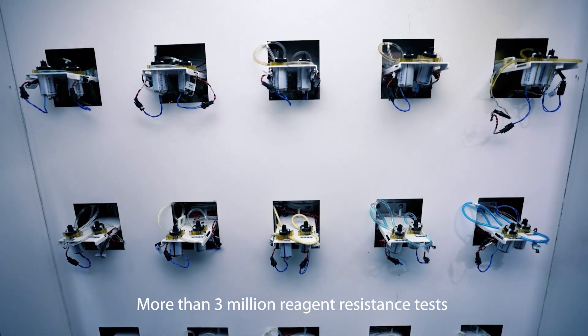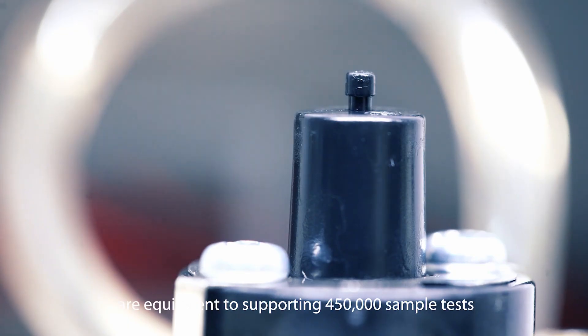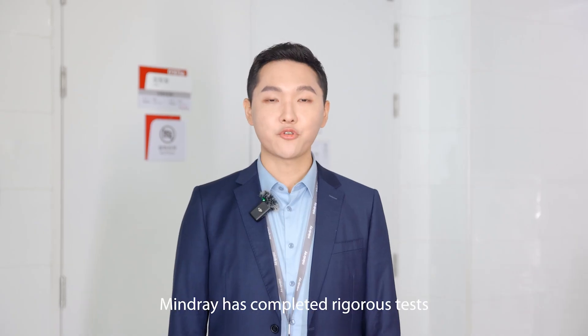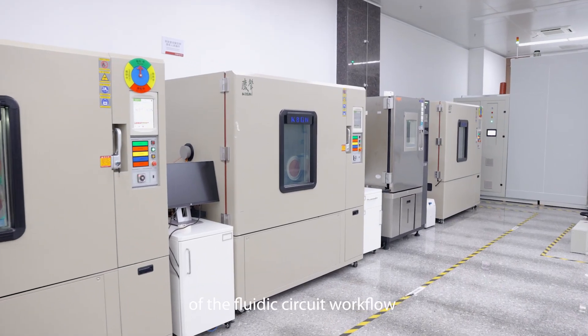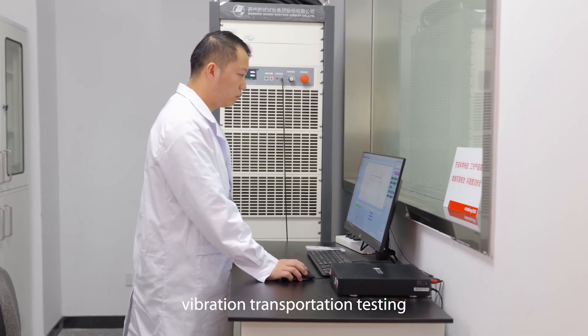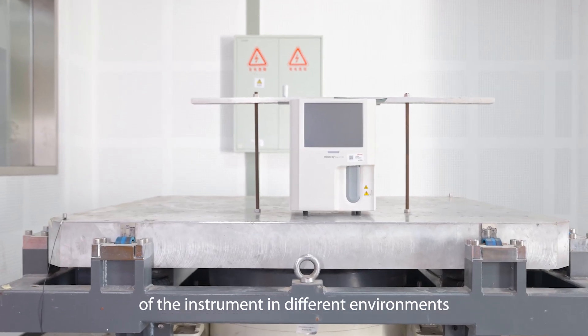More than 3 million reagent resistance tests under pH values between 2 to 11 are equivalent to supporting 450,000 sample tests. Mindray has completed rigorous tests to ensure the reliable design of the fluidic circuit workflow and component connections, such as temperature testing and vibration transportation testing, ensuring normal operation of the instrument in different environments.